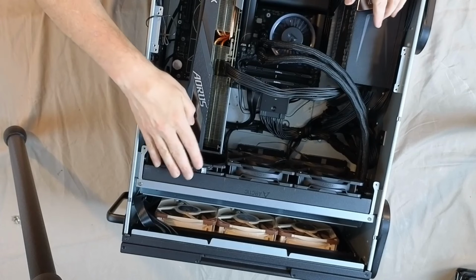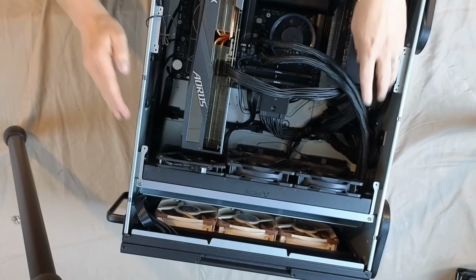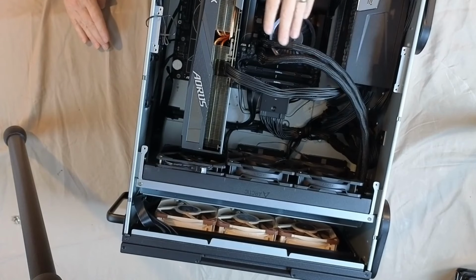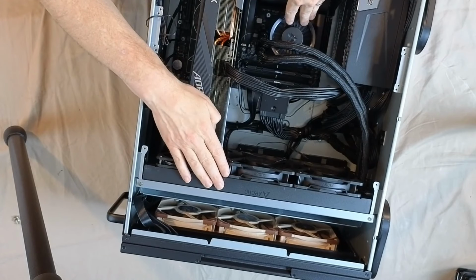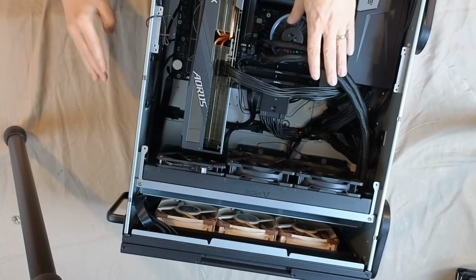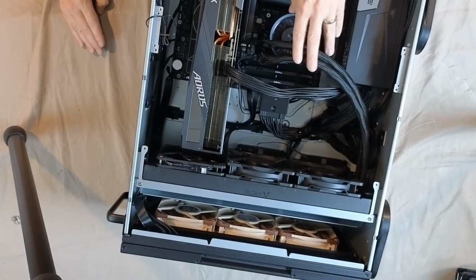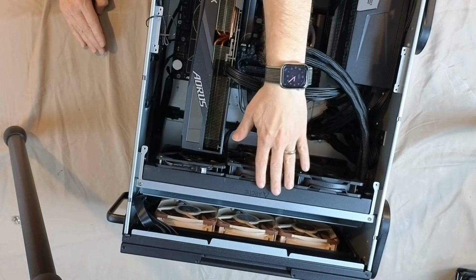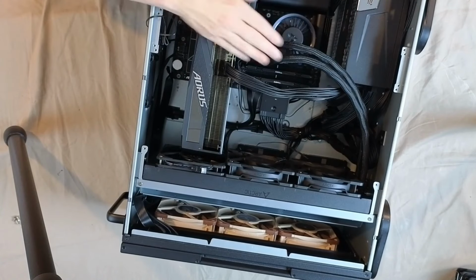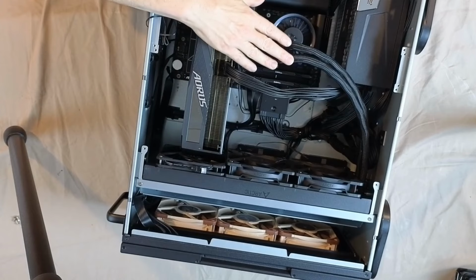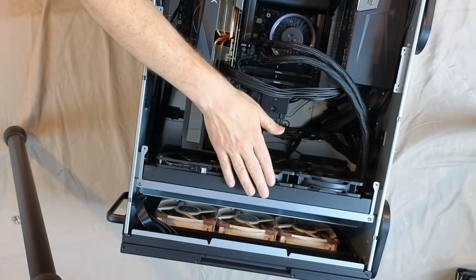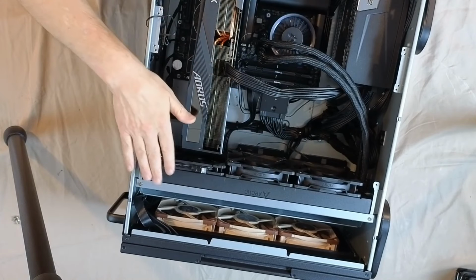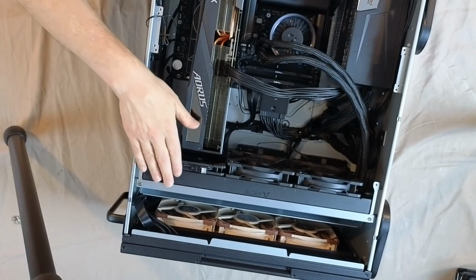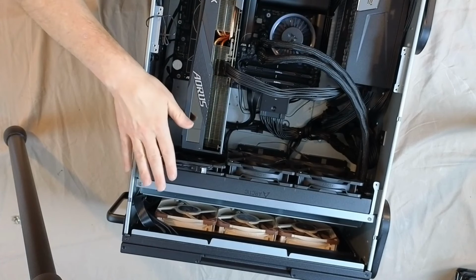With this installed, the pipes come off to the side and down to the pump, so the pump is lower than the height of the radiator, and even the pipes' peak here is lower than the top. This is a safe configuration, so if there are bubbles in the system, they'll collect inside the radiator, probably on this side where the water velocity is less. So this is pretty safe.